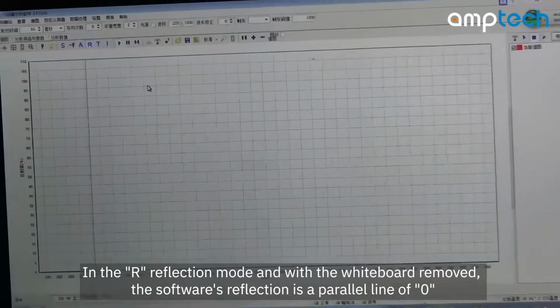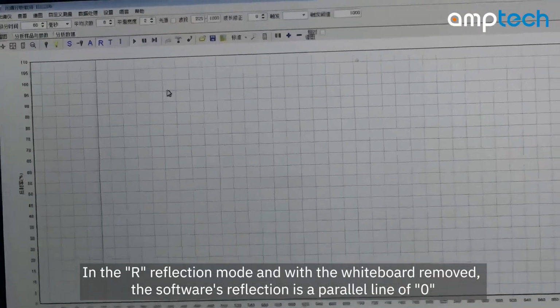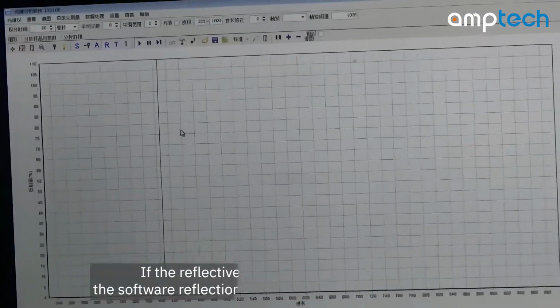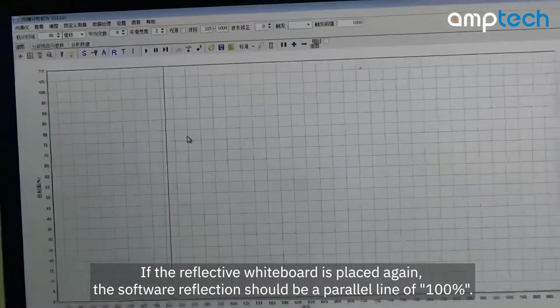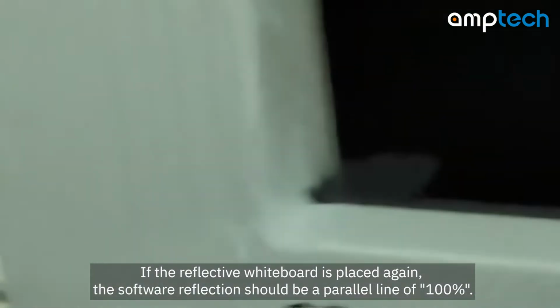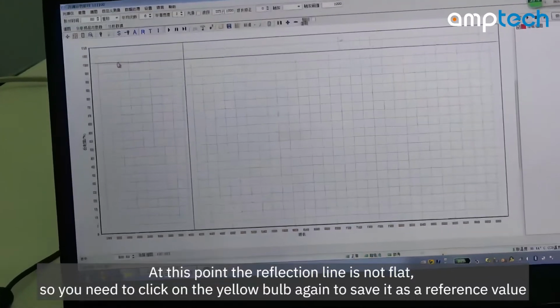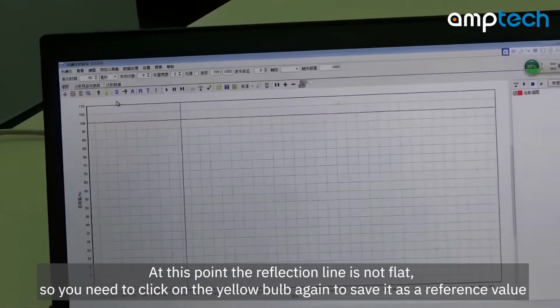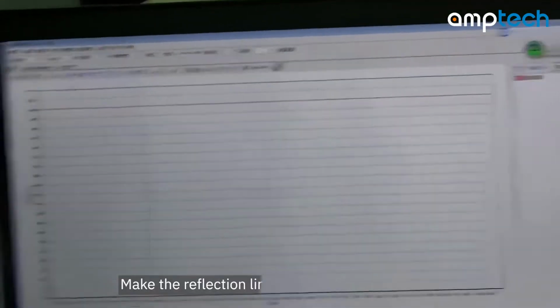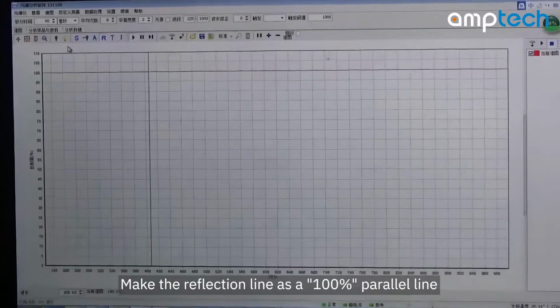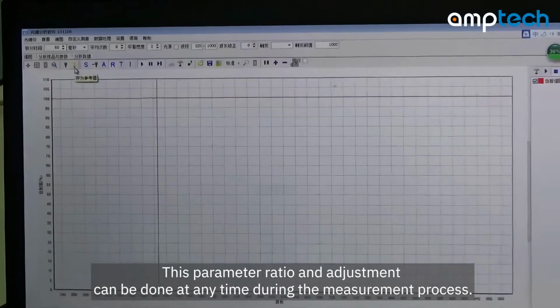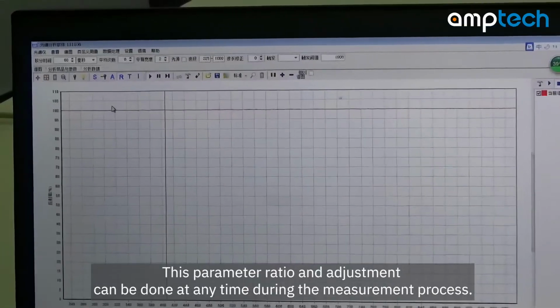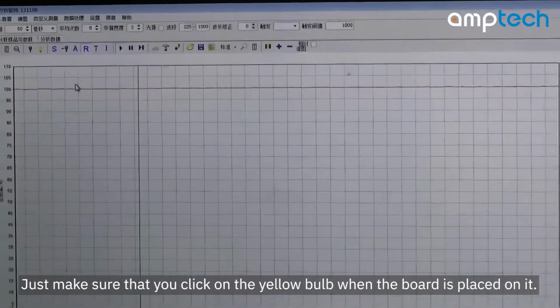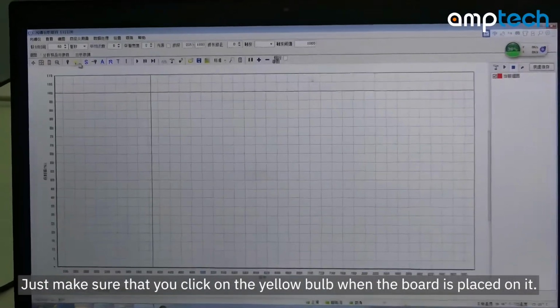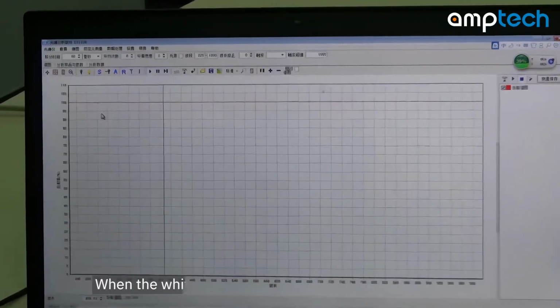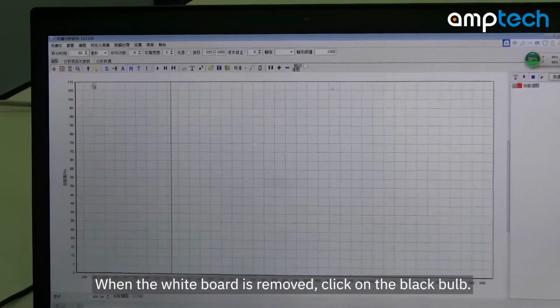In reflection mode, with the whiteboard removed, the software's reflection is a parallel line at 0. If the reflective whiteboard is placed again, the software reflection should be a parallel line at 100%. If the reflection line is not flat, you need to click on the yellow bulb again to save it as a reference value, making the reflection line a 100% parallel line. This parameter comparison and adjustment can be done at any time during the measurement process. Just make sure that you click on the yellow bulb when the board is placed, and when the white board is removed, click on the black bulb.